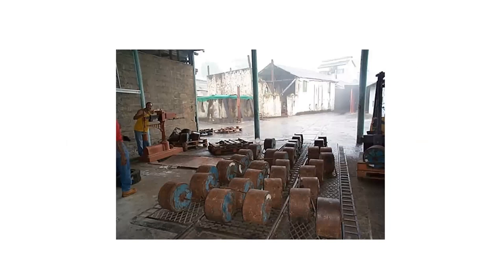If I may just give an example, there was a weighbridge that the Bureau at one time calibrated, and at the end of the exercise, it was found that the weighbridge was out towards the higher end, by almost half a ton, and it had been in operation for about 50 or so years before the Bureau did that exercise. So you could imagine it was out by more than half a ton in favor of the farmers. With the proper application of metrology, that would not have been the case.